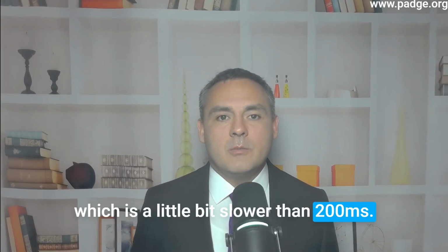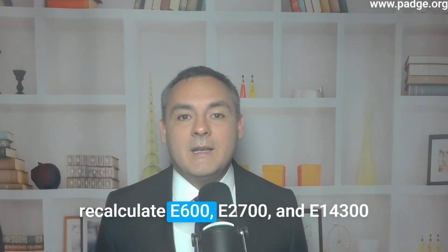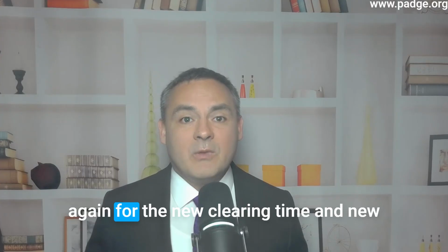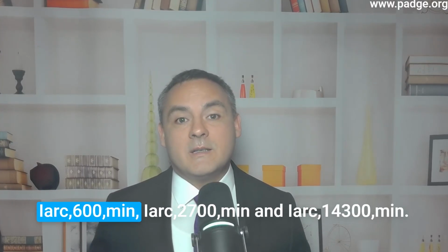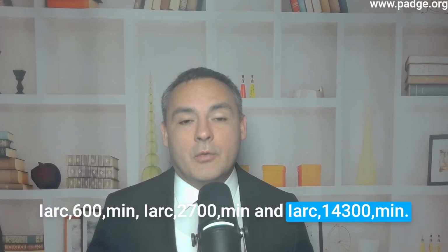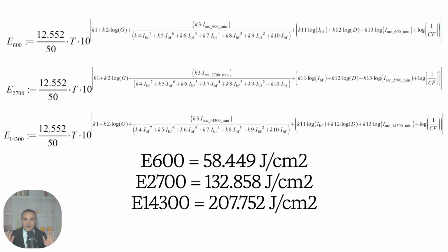than 200 milliseconds. So what we have to do at this point is recalculate E600, E2700, and E14300 again for the new clearing time and new IARC 600 min, IARC 2700 min, and IARC 14,300 min. The equations are exactly the same as before.